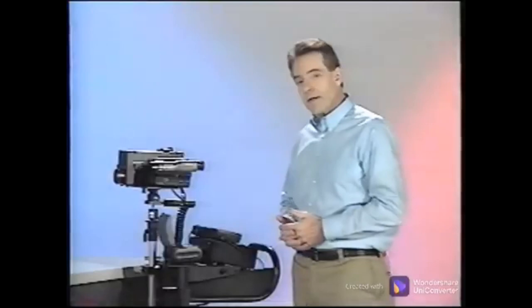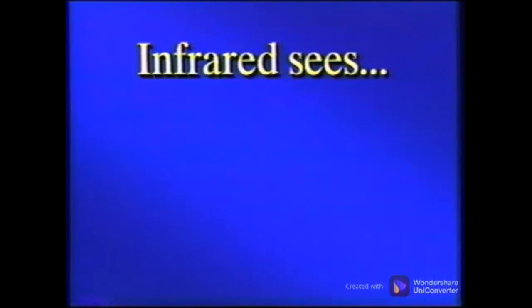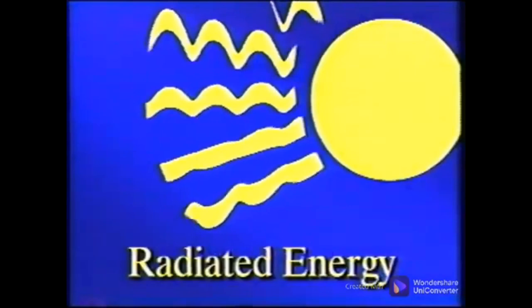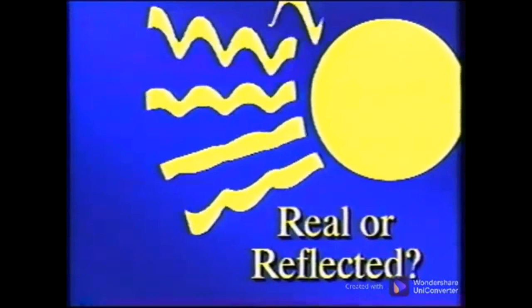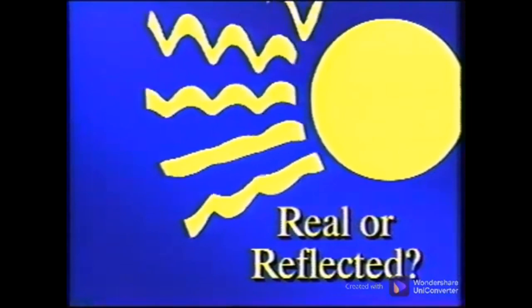Whatever system you use, there are certain considerations that must be made in order to make accurate temperature measurements. Remember that the infrared camera is used to look at objects that may be hot, cold, or near ambient temperature, and that it actually views the radiated energy. This radiated energy can be real and provide an accurate representation of the object. However, the radiated energy can be reflected from another source and provide invalid images and temperatures.